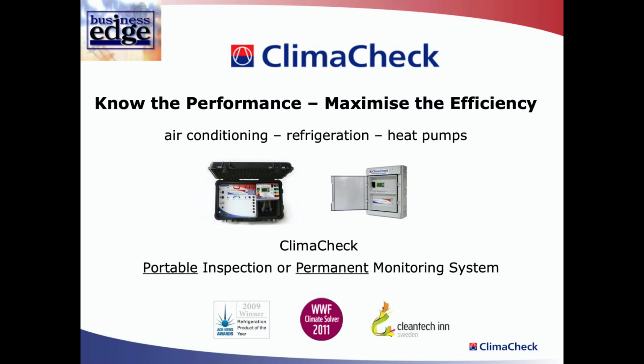The permanent version is shown on the right hand side and is configured to suit the type of equipment that you're working on. So twin circuit water chiller with economizers, oil coolers, and whatever you wish. This is configured to record all the data, to transmit it through the customer's LAN if it's available, or with the integral modem to transmit the data to our web service, where the server records the data and stores it for a minimum of 2 years. That enables you to go online today and see exactly what's happening on your iPhone or your smartphone, on your computer, from anywhere in the world, and indeed then go back in time and look at the performance over any period of time over the last 2 years.